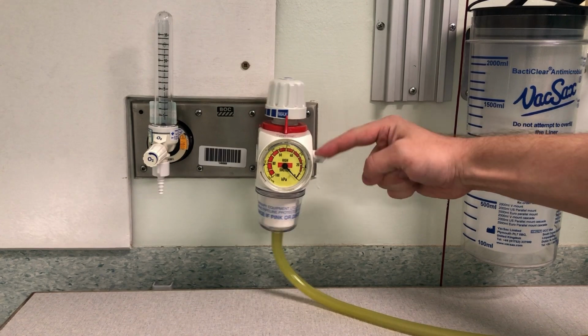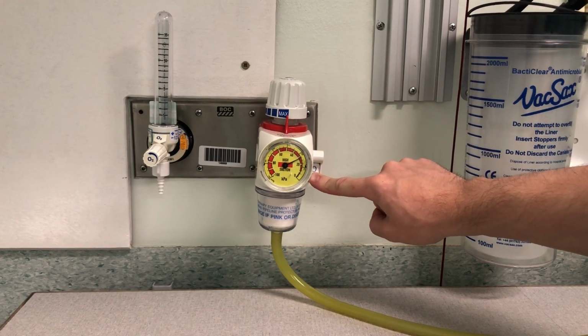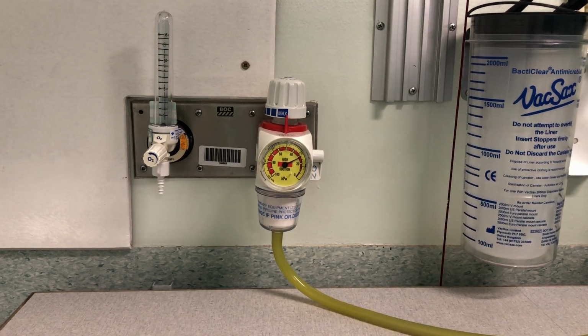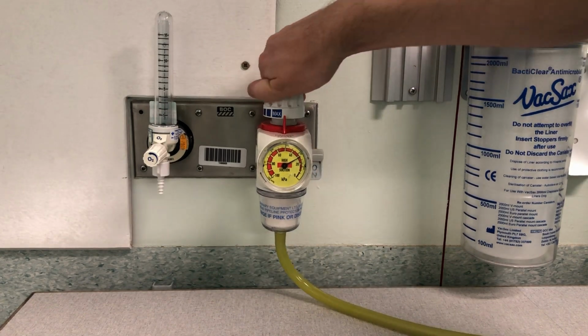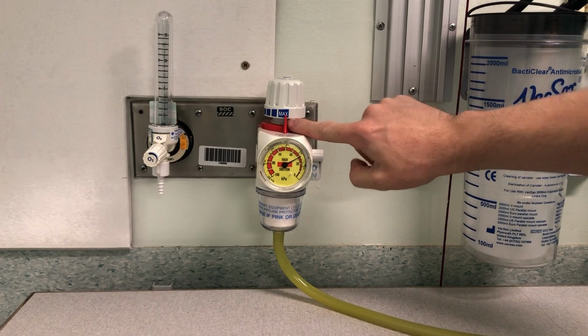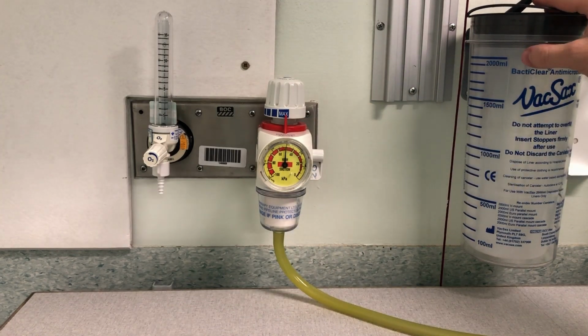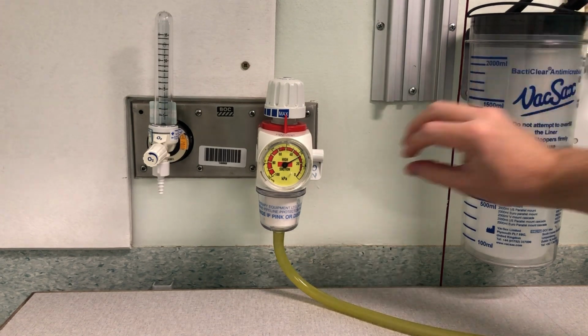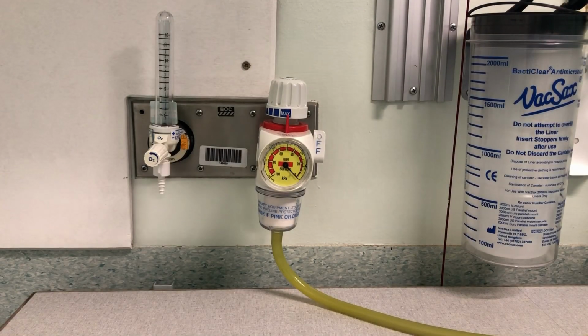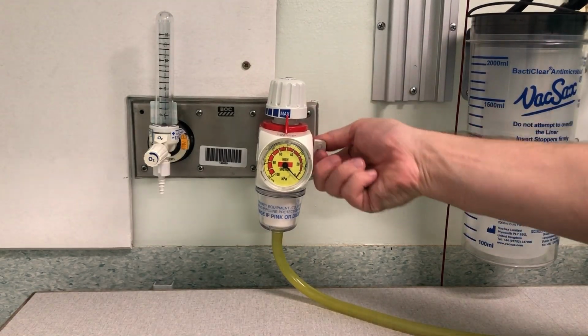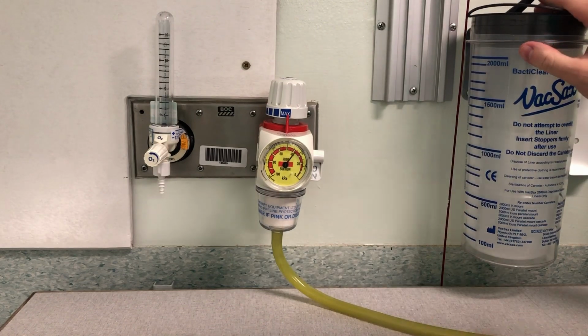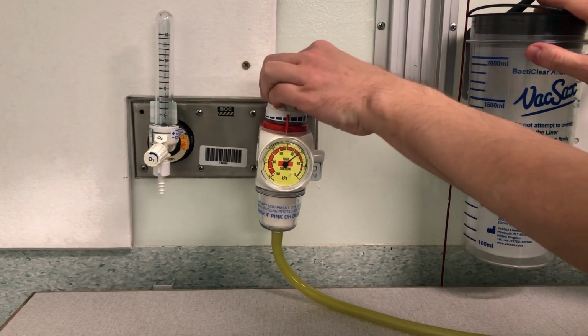So to check the device is working, switch the suction controller on, set to its maximum pressure and occlude the VACSAX liner port. Watch the needle freely move to above 60 kPa. Release the occlusion and watch the needle drop freely to about 10 to 20 kPa, and switch the controller off and witness the needle fall to 0. High vacuum suction controllers should be left set up to 20 kPa, ready to use, and they are only to be used for suction.